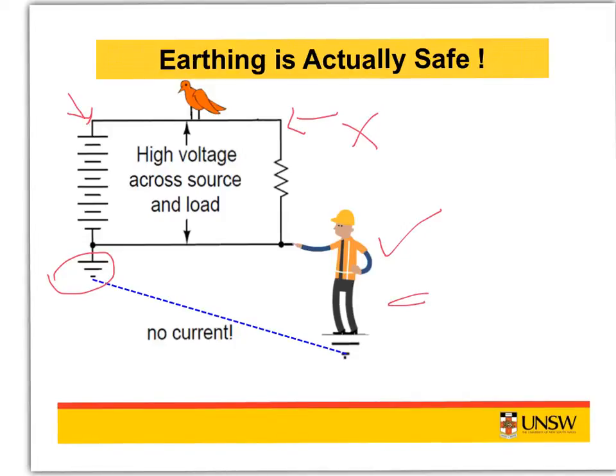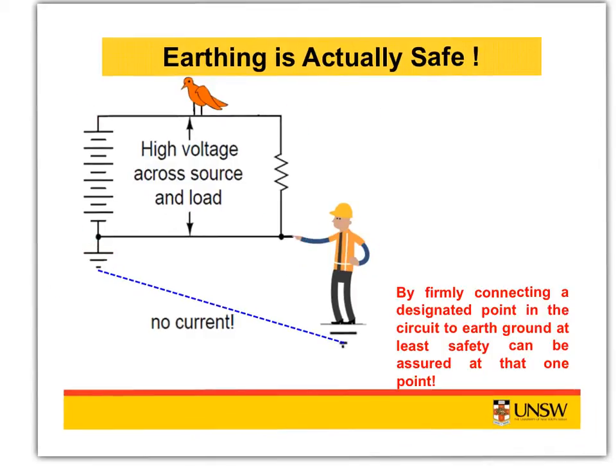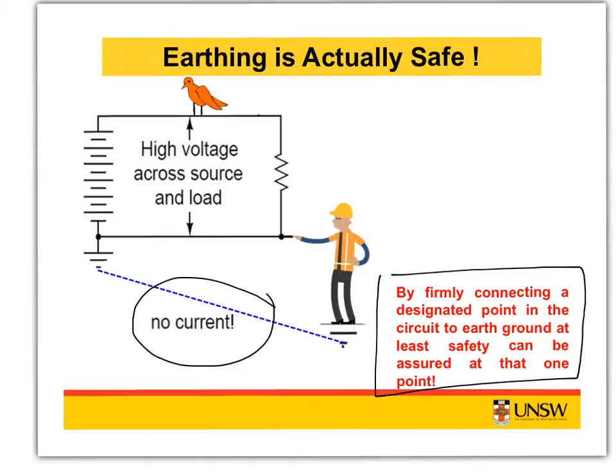ever get shocked. Thus, the presence of an intentional earthing point in an electric circuit is intended to ensure that at least one side of it is safe to come in contact with. So this neutral point is always safe to come in contact with. Therefore, the conclusion here is that by firmly connecting a designated point in the circuit to earth ground, at least safety can be ensured at that one point because there is no current in this path. Why? Because this point and this point are at the same zero potential. So current can never flow through the same potential points.